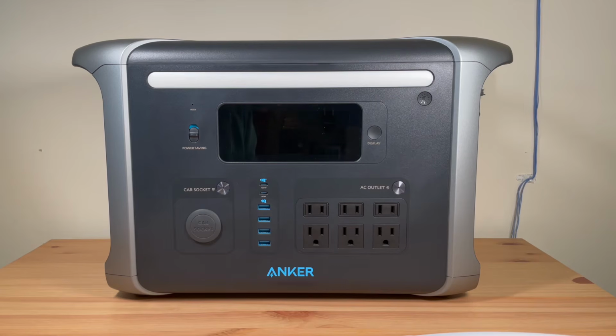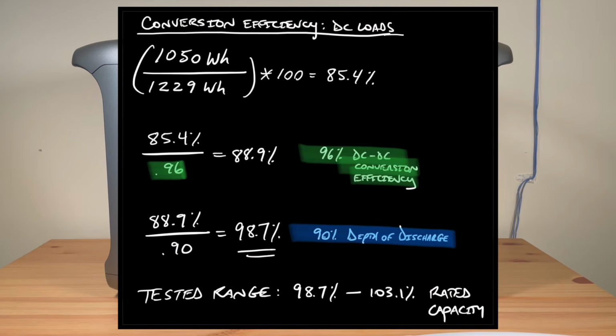If we take all these and divide by 0.90, to indicate we've only used approximately 90% of the battery's capacity with 10% in reserve as depth of discharge - just to take one example, the 1,050 on the DC side divided by 1229 gets us to 85%. Divide that by 0.96 and we're at 88%. Then divide that by 0.90 and it gets us to 98.8%. So we're basically right at the capacity of this battery.